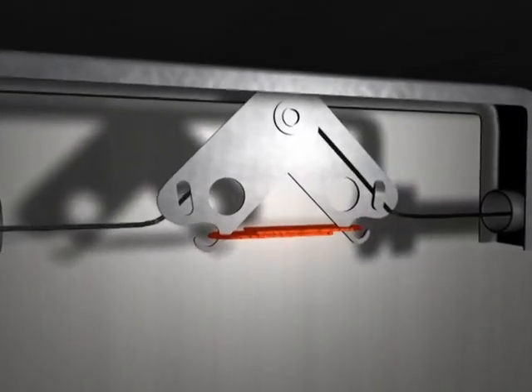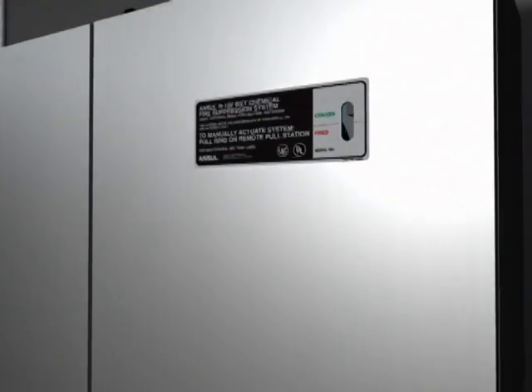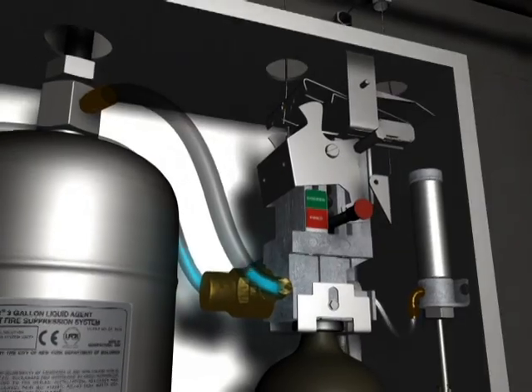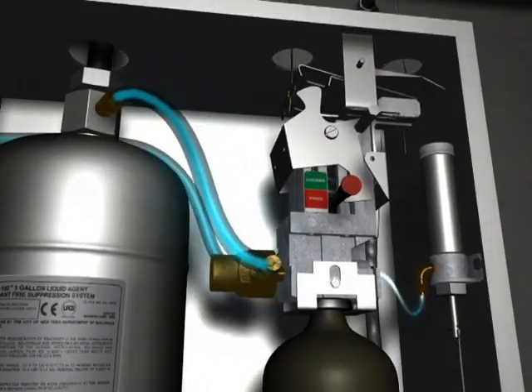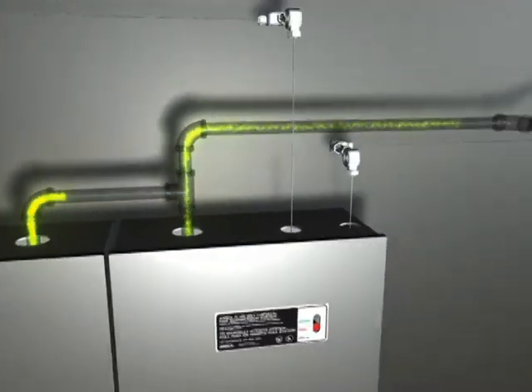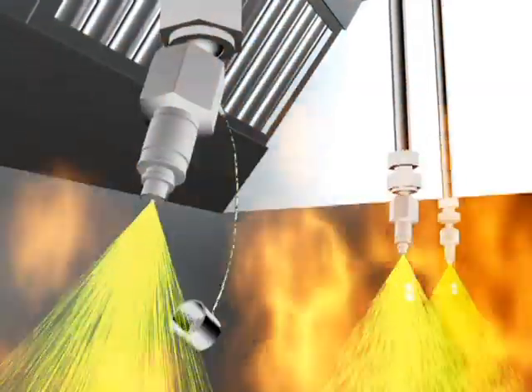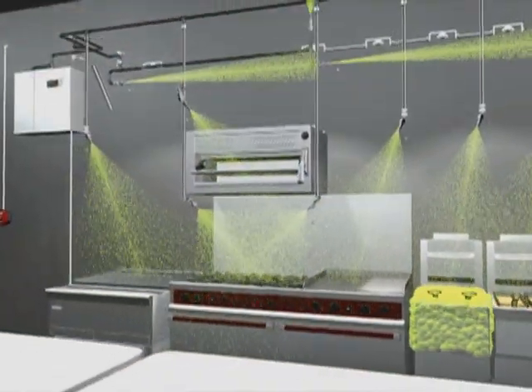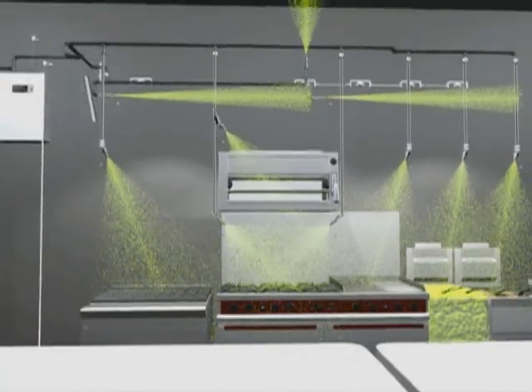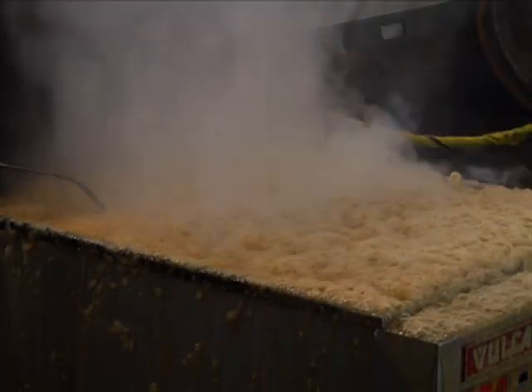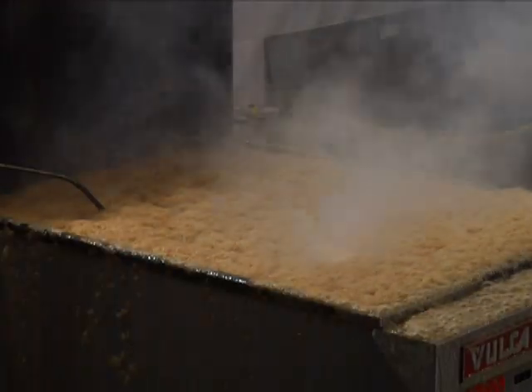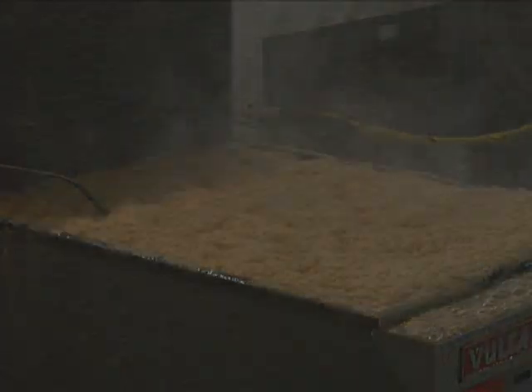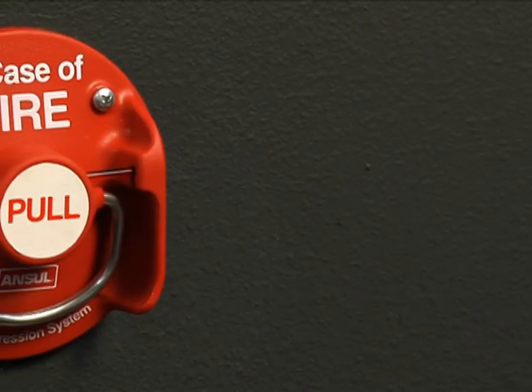In the event of an actual fire, the fusible link detection system responds rapidly to the growing heat. When the temperature rating is exceeded, the fusible link separates, triggering the release of a compressed gas cylinder within the ANSUL release mechanism. Simultaneously, the compressed gas pressurizes the ANSULEX agent tank and an air cylinder that trips the ANSUL mechanical gas shutoff valve. The ANSULEX agent is then dispensed throughout the system, rapidly knocking down the flames. And because it has a neutral pH factor, ANSULEX is gentle on kitchen equipment as well. To help prevent fire reflash, the agent creates a foam blanket that inhibits the release of flammable vapors and cools the hazard area.